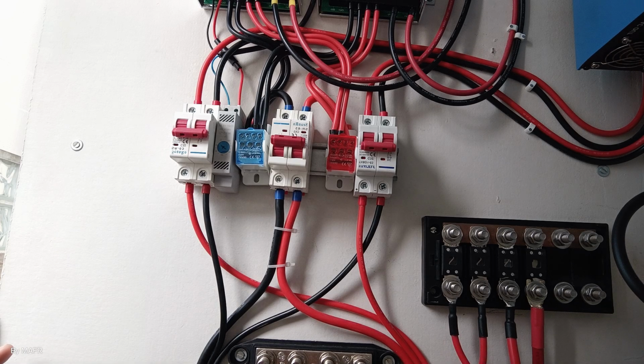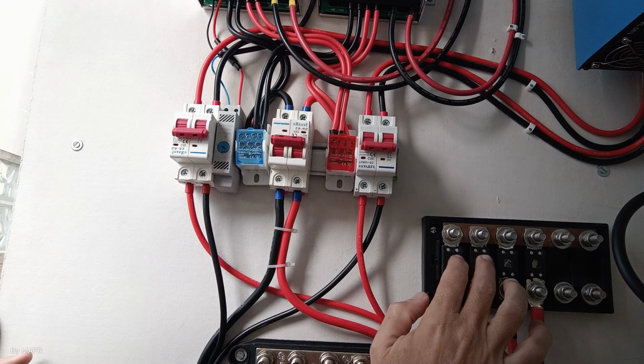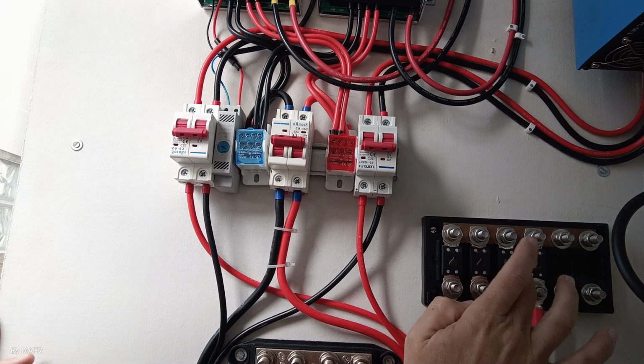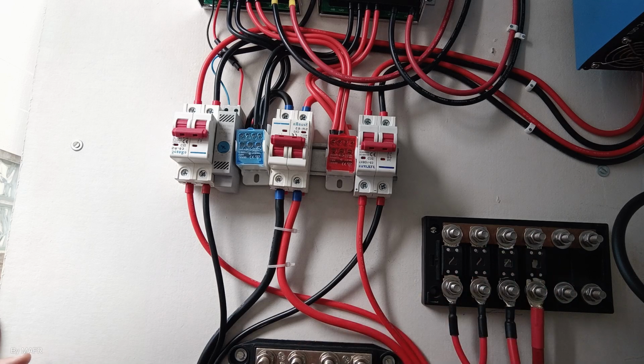And then I have the two inverters connected here, and the maximum that they can pull from the system is 40 amperes. On those I have a fuse of 40, and on the charge controller I have a fuse of 60 amperes. As I said before, the maximum I can get here is 50 amperes.